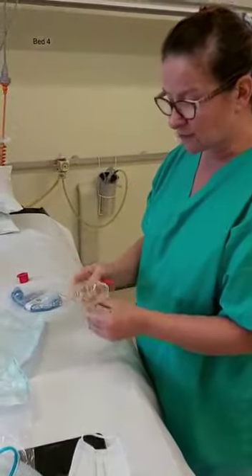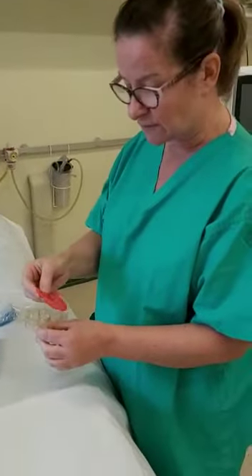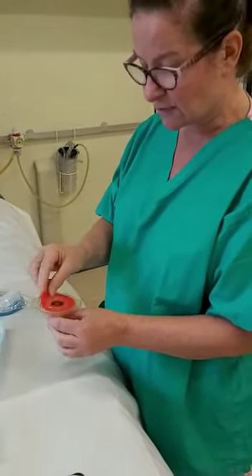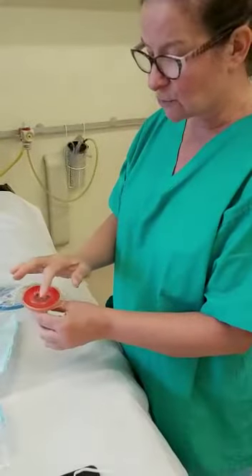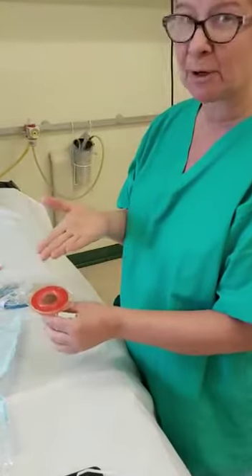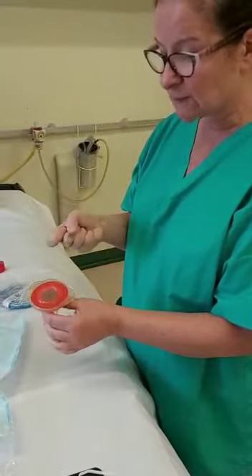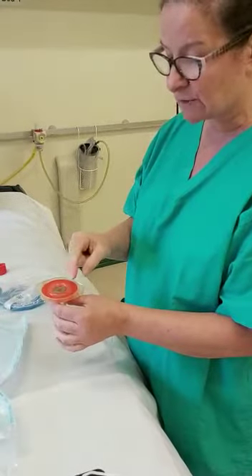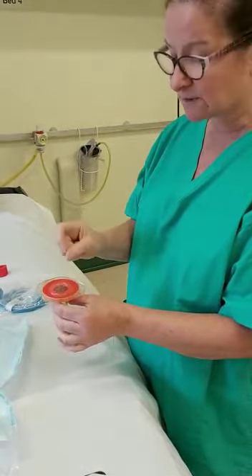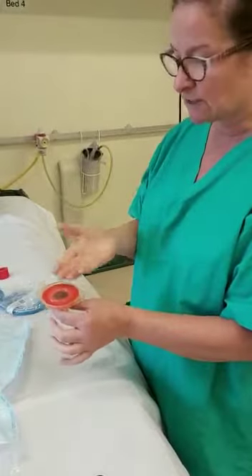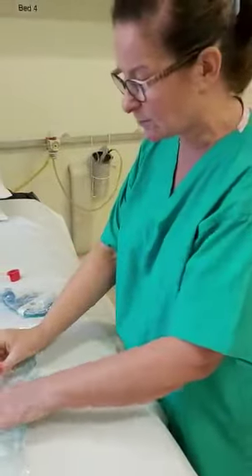So when you insert your expiratory valve, the diaphragm just sits on the top in that little lip, and it's always important to have the metal disc uppermost. If you get problems when calibrating, sometimes it can be because people have put the diaphragm on upside down with the metal disc down. So always make sure the metal disc is uppermost.